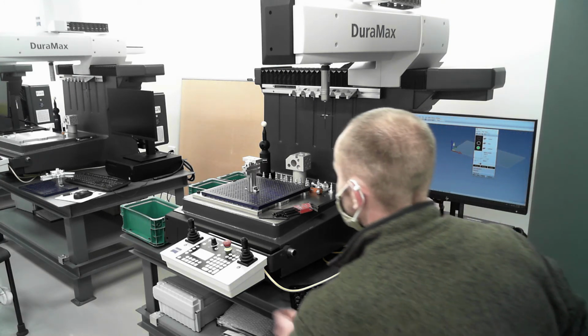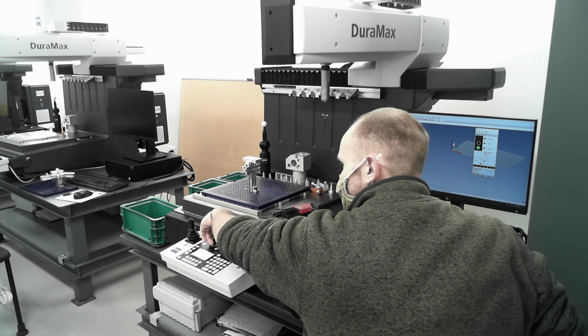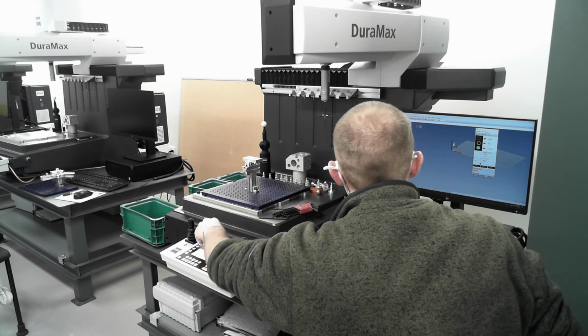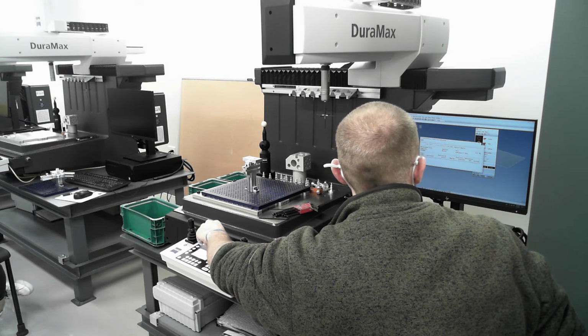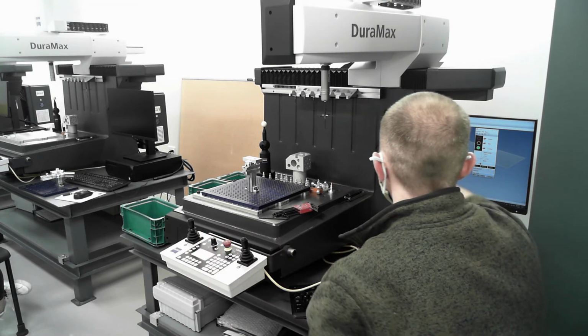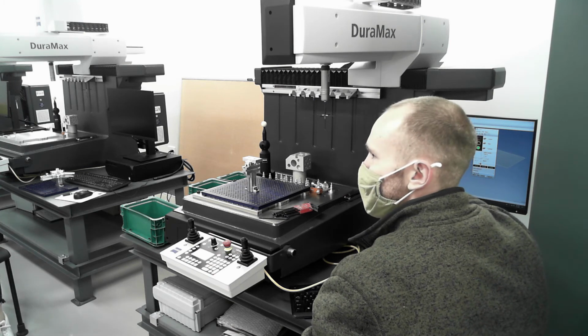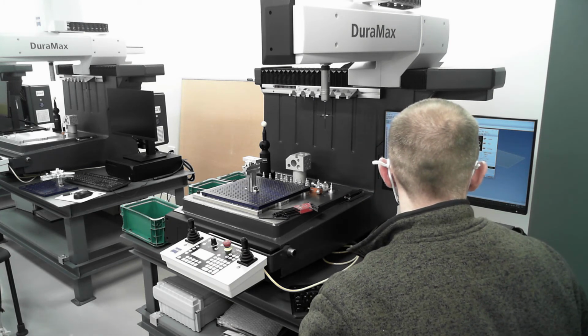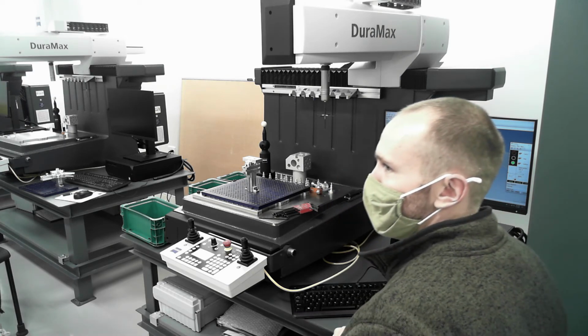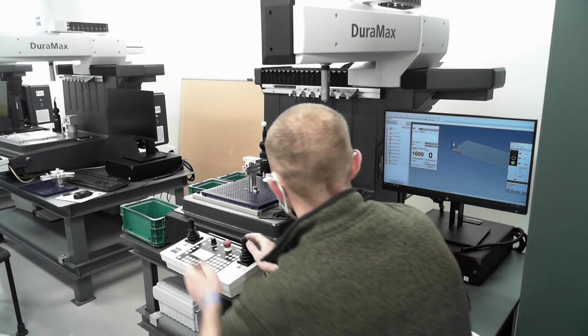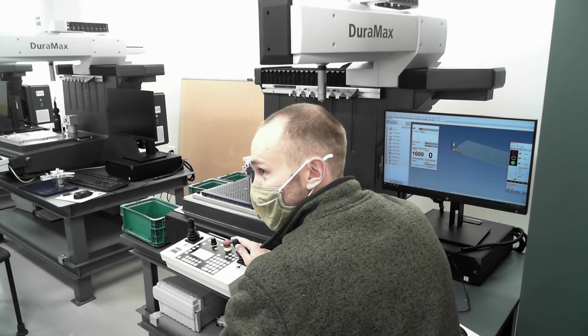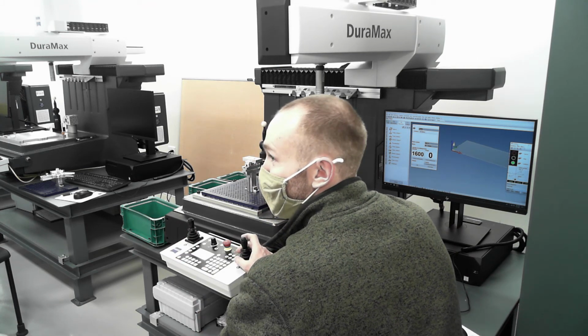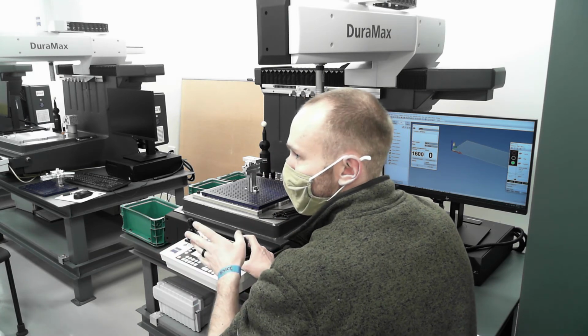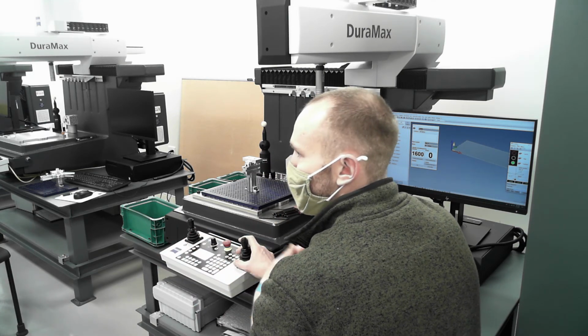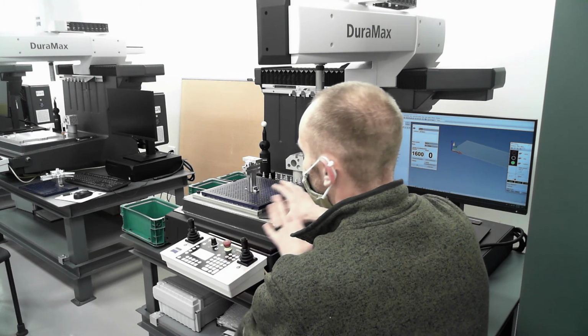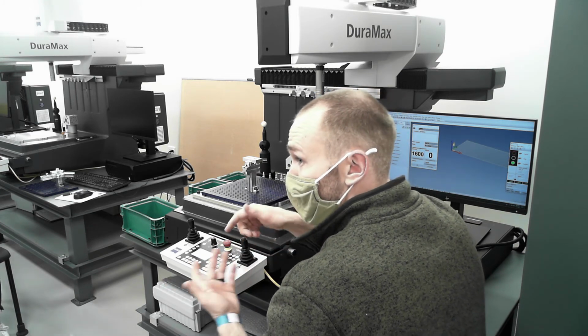So I'll hit start. Got my thumb on the speed slider here, my hand on the speed dial. And the first thing it asks me to do is the manual alignment. So it wants me to take 1,600 points on whatever surface is shown in gray here. So this might take us till the end of class. I'm just kidding. We're not actually going to take that. We're going to take 3 alternative. The minimum number of points for a plane is 3, so we'll take 3. You only need to take the minimum. You can take more than that if you'd like, but I always take the minimum because this is just a rough alignment, as you'll see. The machine will go back and reprobe all of this.